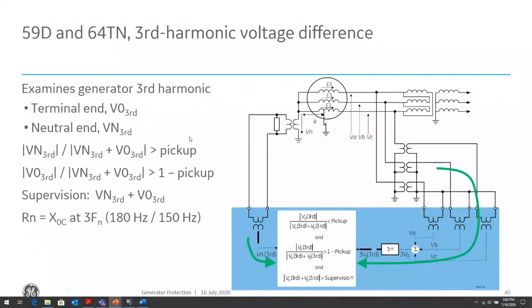So the more reliable method that we have is the third harmonic voltage differential or difference. What this method is, we're going to look at the terminal voltage third harmonic and the neutral third harmonic, and we're going to do a differential. So it's similar to the current differential, it's a voltage differential on the third harmonic voltage.